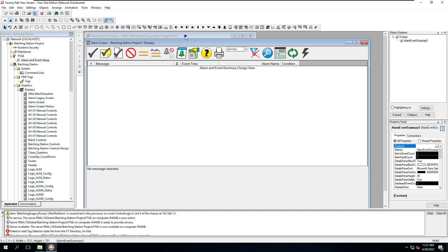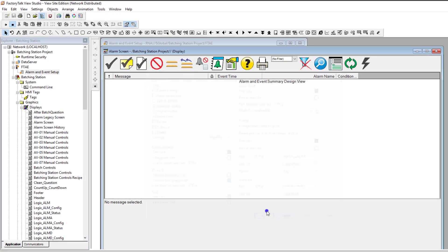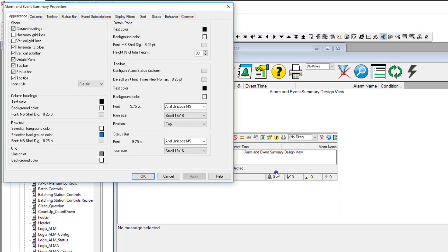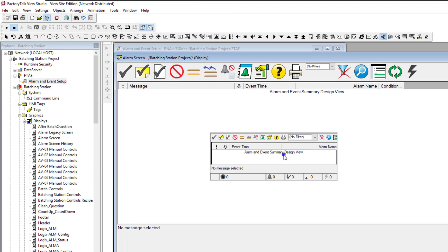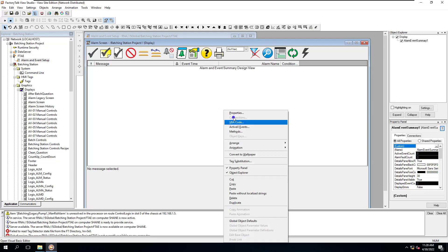If you use the legacy tag alarm screen, it will still work if you still have the tag in there, but those screens are no longer going to work in Factory Talk 12 or above. You have to use the new alarms and events summary screen. When you see the properties, all it is is an 'alarms and events summary.' Go into your HMI systems, add alarms and events setup, choose summary, and populate that. It's really simple. If it's your first time converting, it may be best to use zero filters to get everything converted, then come back and add filters later.